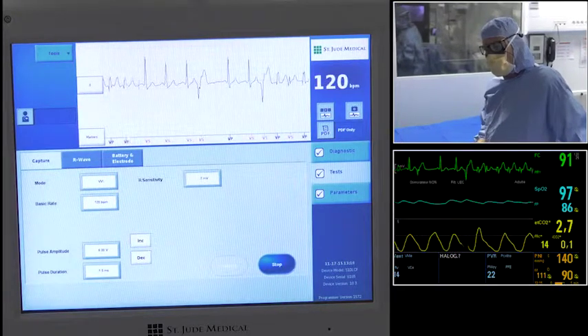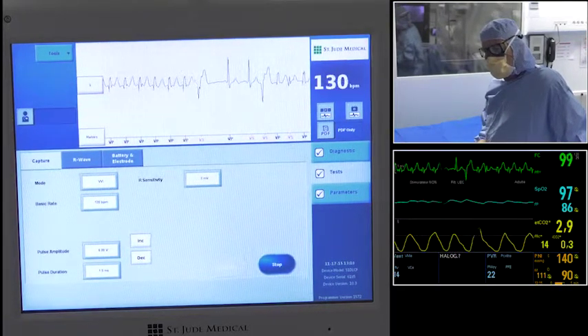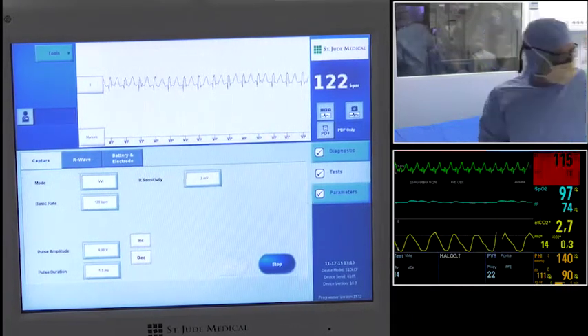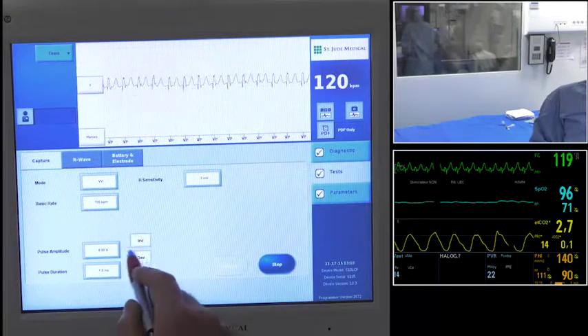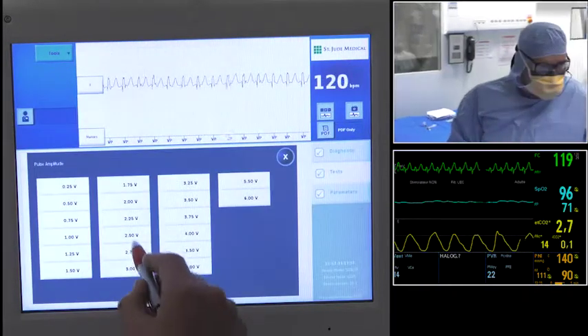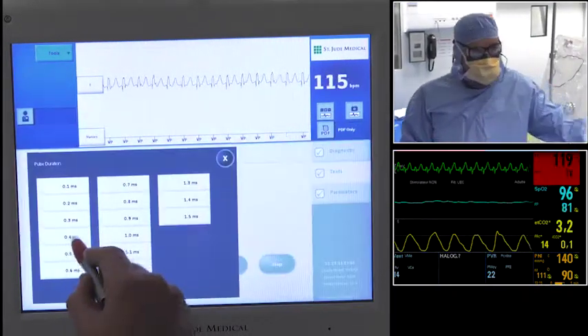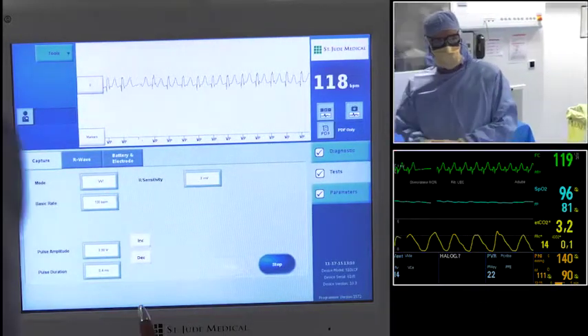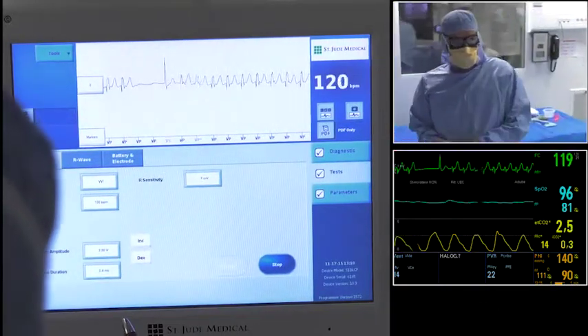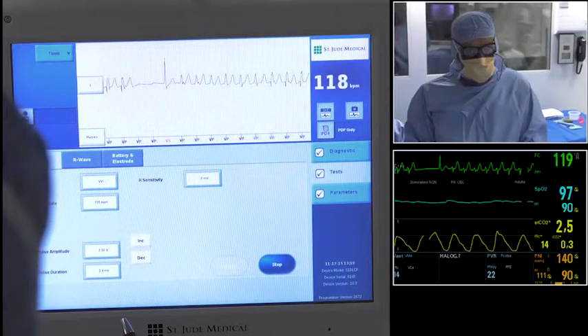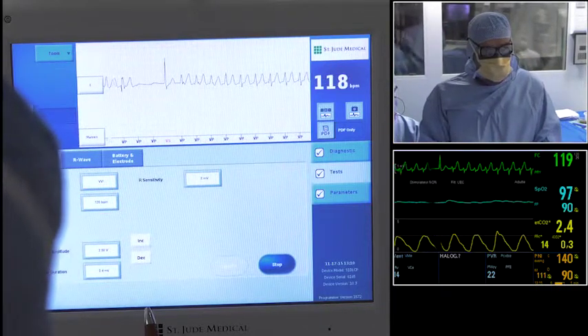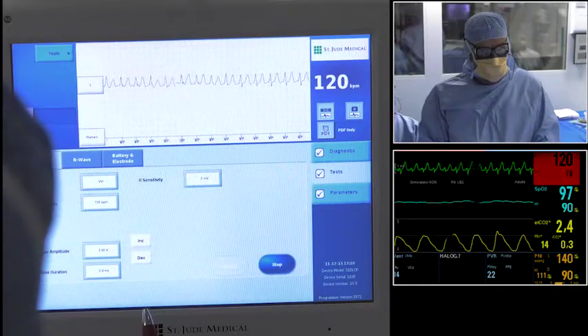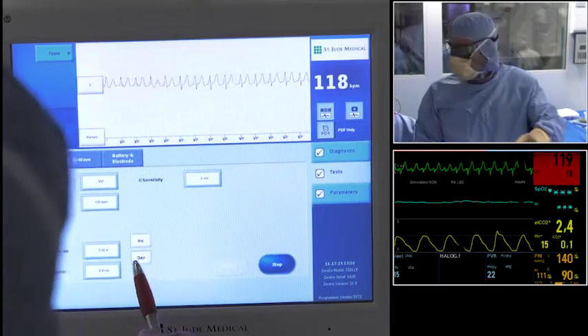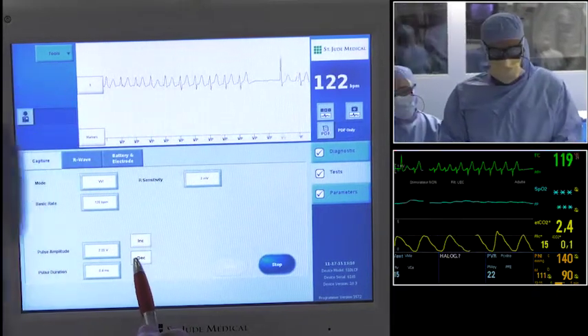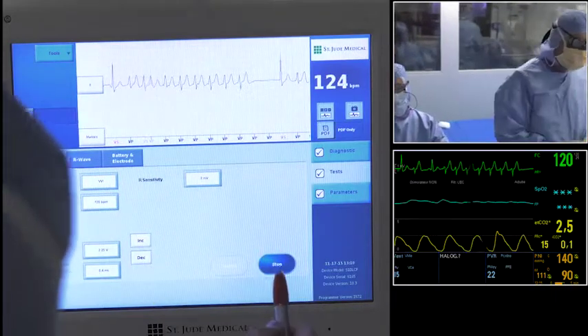Screwed the nanostim. 6 volt, 1.5 millisecond is maximum output for phrenic stimulation. So we check for the phrenic capture. No phrenic capture, so it's okay. So down to 2.5 volts, 0.4 milliseconds. 2.5, loss of capture. We had the loss of capture, but now it's capturing. Okay. So 2.5... 2.25, so we got a loss of capture.